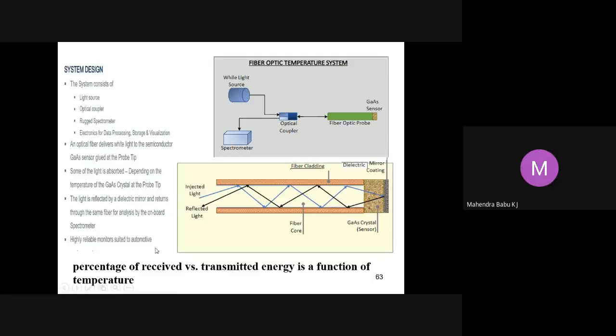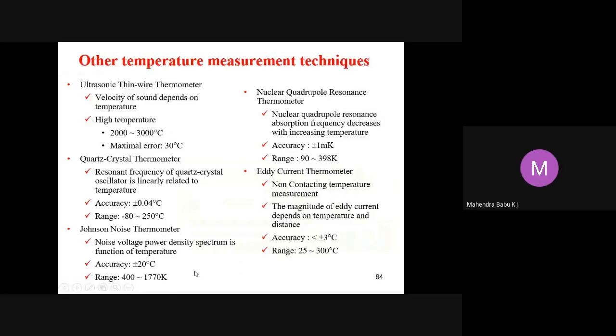Highly reliable monitors suitable for automotive. So here the percentage of received versus transmitted energy is a function of temperature. Other temperature measurement techniques are the ultrasonic thin wire thermometer, where the velocity of sound depends upon the temperature, high temperature range 2000 to 3000 degrees Celsius, maximum error is 30 degrees Celsius.